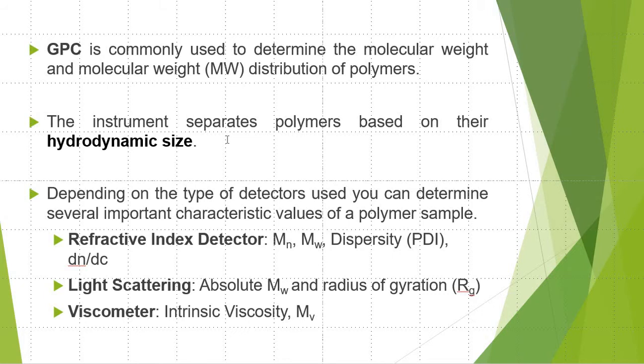In multi-detector GPC systems, you'll often find a light scattering detector along with the RI, which allows you to calculate the absolute molecular weight and radius of gyration. A viscometer can provide additional insight by providing the intrinsic viscosity and viscosity average molecular weight.